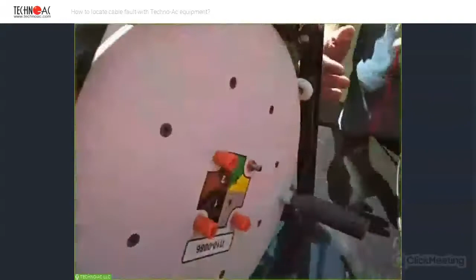So let me start with electromagnetic cable fault location. Generally, this method is similar to cable tracing or cable location because you have to connect your transmitter somewhere in order to locate the cable itself and in order to locate the fault of this cable. So let us do the following. I will open one of the cores of the cable and connect our transmitter to it right away, like this.